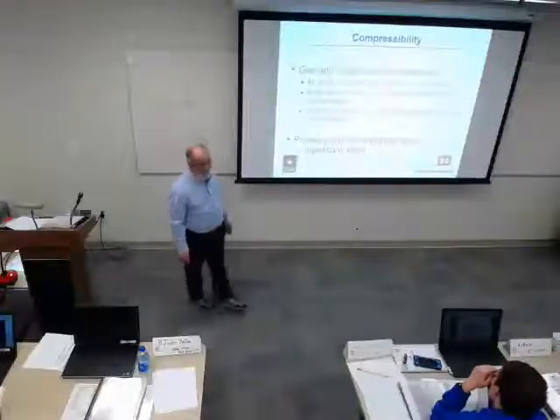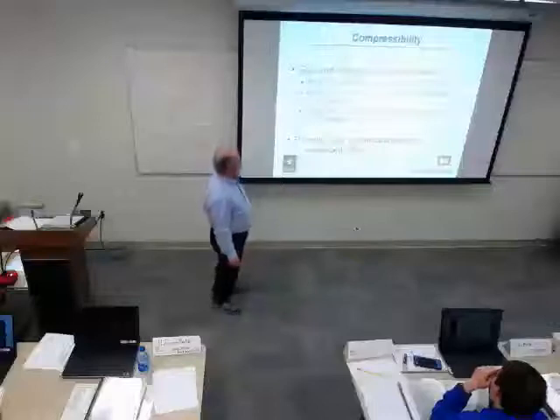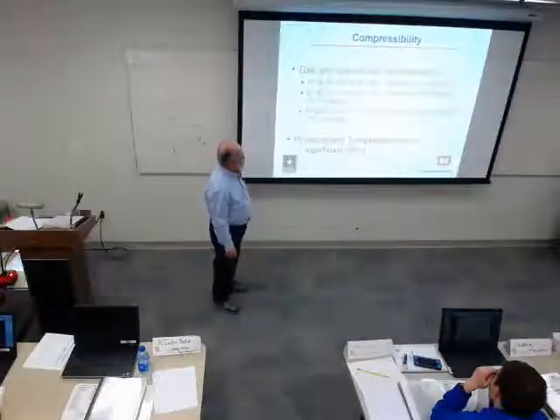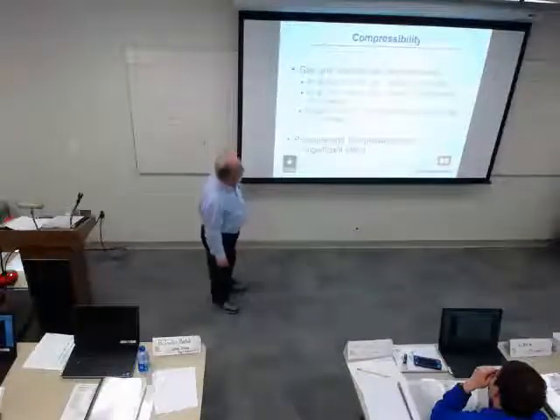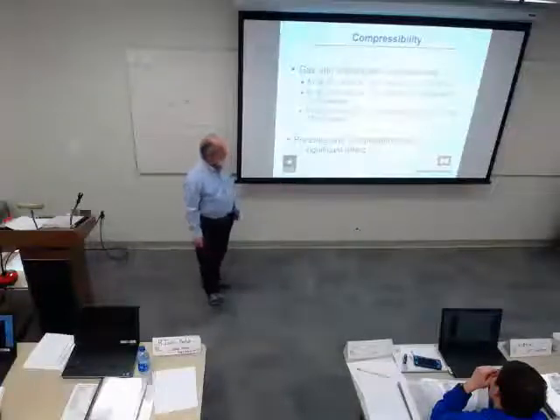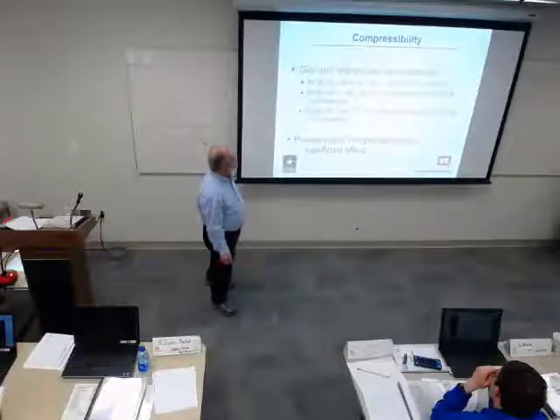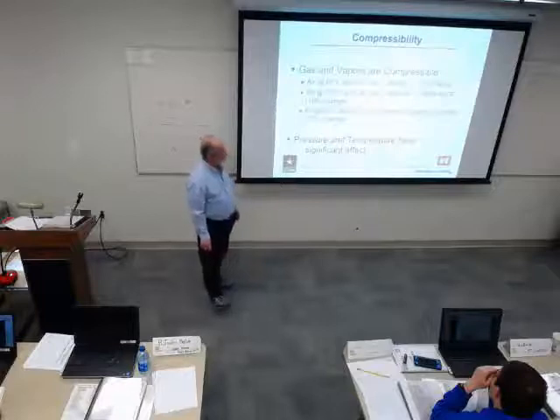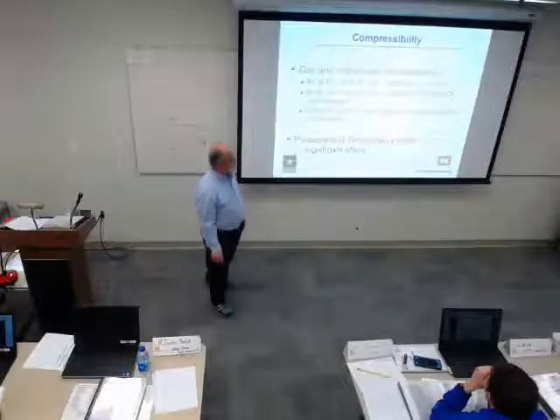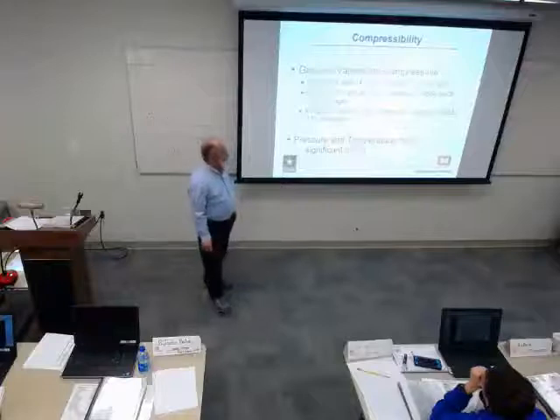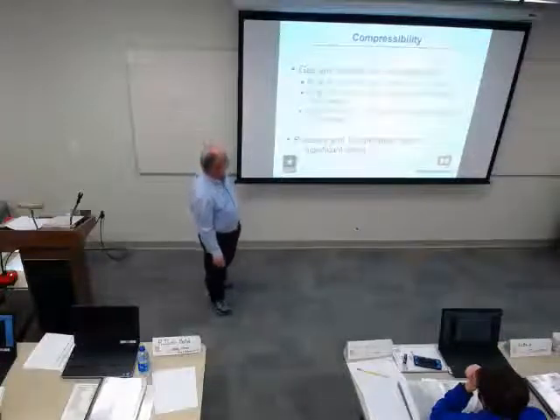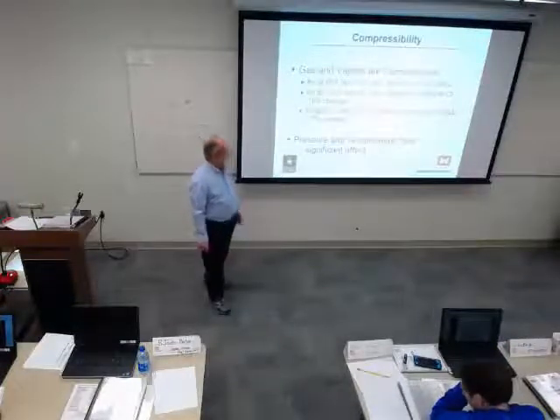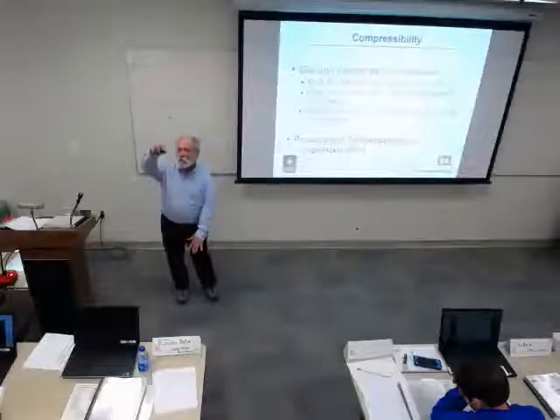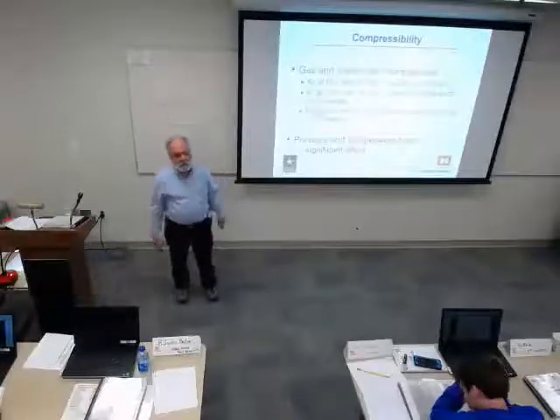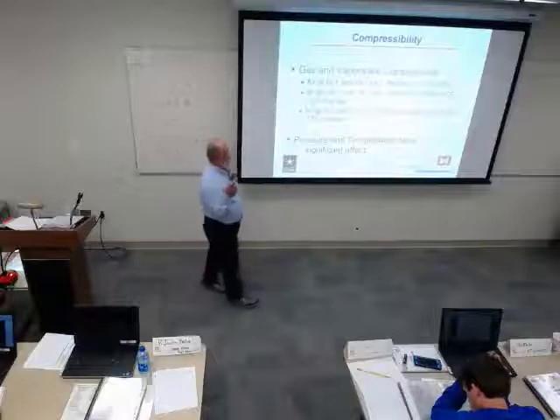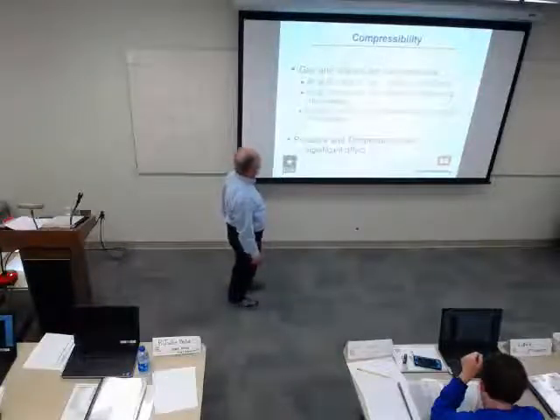Gas and vapors are compressible, so their life is a little different. At 60 degrees Fahrenheit and 14.7 psi, the density of air is 0.0763. At 120 degrees Fahrenheit, at the same pressure, the density is 0.0684. So we've got a 10% change in density. That means its specific volume went up. That stands to reason. It expands as it's heated.